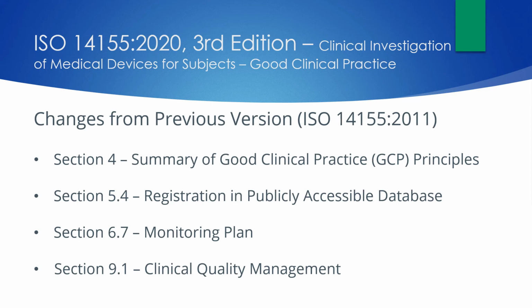Section 6.7, which is the monitoring plan, has an inclusion of risk-based monitoring, specifically that the sponsor shall determine the extent and nature of monitoring based on the risk assessment. This requires that the results of the risk assessment be used to develop a risk-based monitoring plan and a supporting rationale. Section 9.1, clinical quality management. This has an inclusion of guidance with regards to clinical quality management, specifically to ensure that the clinical investigation is designed, conducted, and monitored, and that the data generated, documented, recorded, evaluated, and reported is in compliance with the standard, the clinical investigation plan, and any subsequent amendments, along with any applicable standards or regulatory requirements.